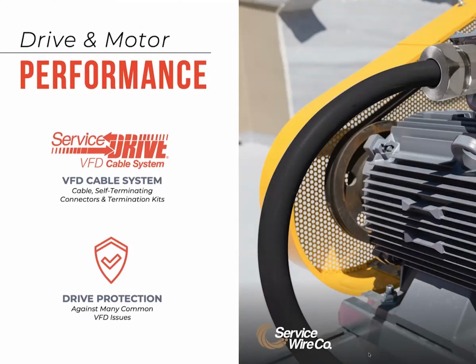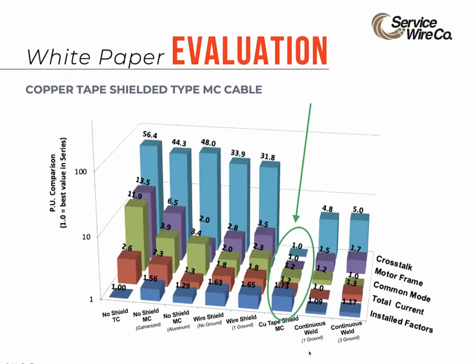While there are dozens of VFD cable constructions on the market, ServiceWire's Service Drive VFD cable system is the only proven solution to address the common issues affecting drive performance. In third-party testing by IEEE fellow John Bentley and senior member Patrick Link, the pair concluded that a copper tape shielded Type MC cable significantly outperformed the other cables in nearly every category: crosstalk, motor frame, common mode, and total current. And now with the system's new self-terminating connectors and termination kits, Service Drive has addressed the installation factors from this study.